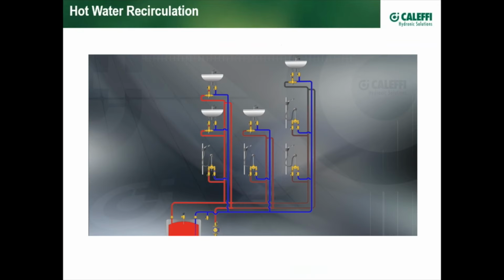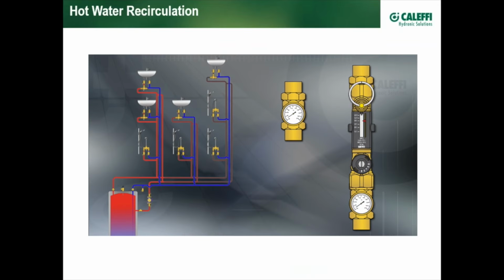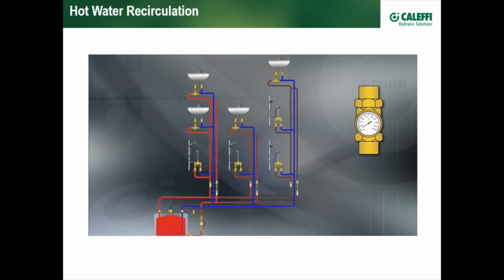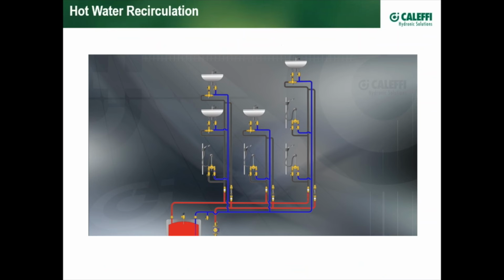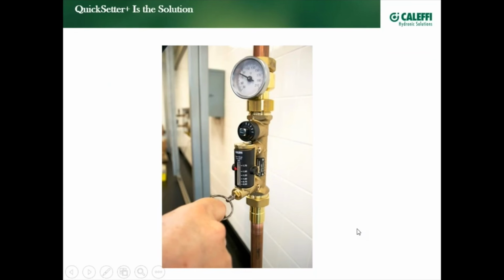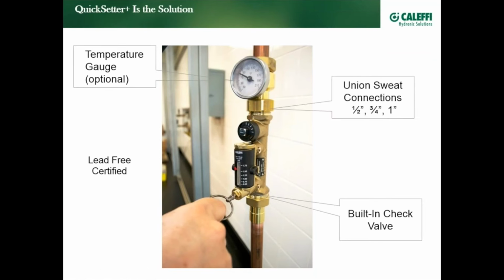Now, balancing isn't relegated only to hydronics, you'll agree. Hot water recirculation in a plumbing system is another popular application, especially these days where water is more scarce. So rather than let an opportunity, when you turn on a hot tap, for water to be wasted waiting for the warm water to come, balancing valves are used, such as here. And the Quick Setter series called the Quick Setter Plus is ideal in doing that. Pull, adjust, and now in seconds, the plumbing engineer or designer has made sure that his risers are getting the proper flow of recirculation water.